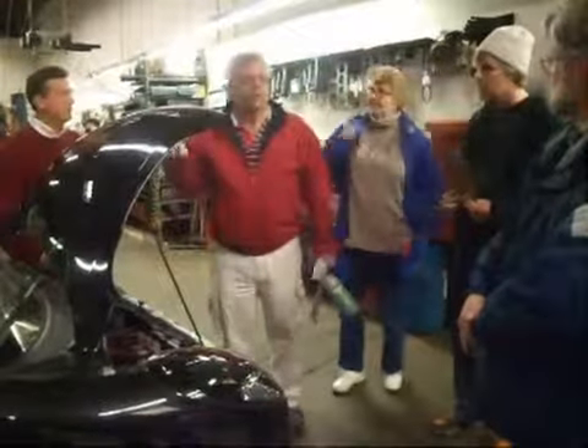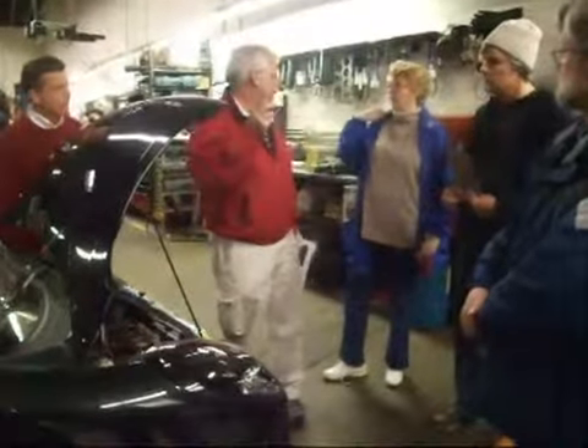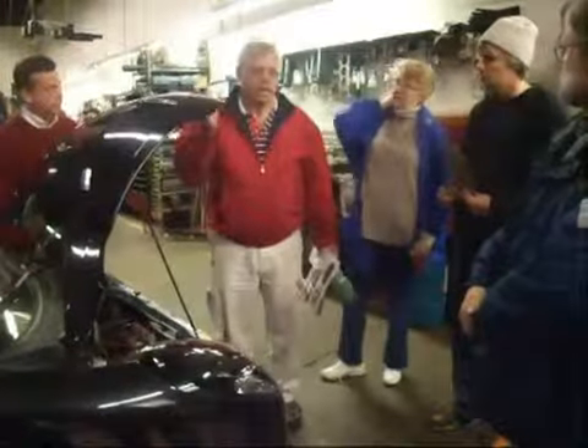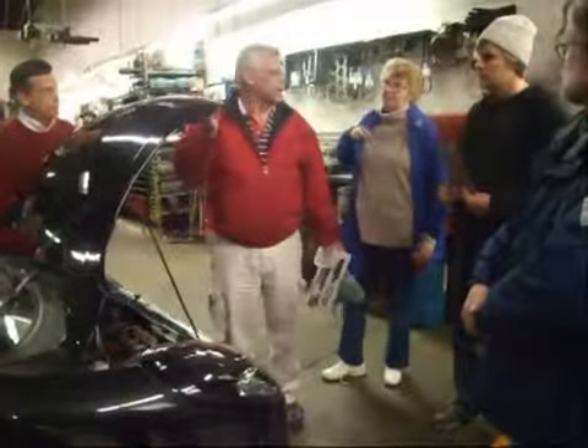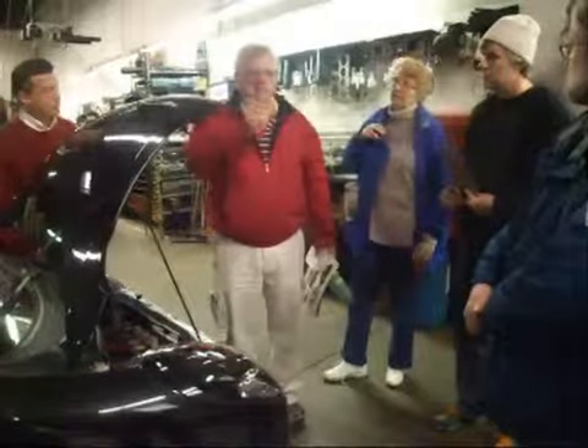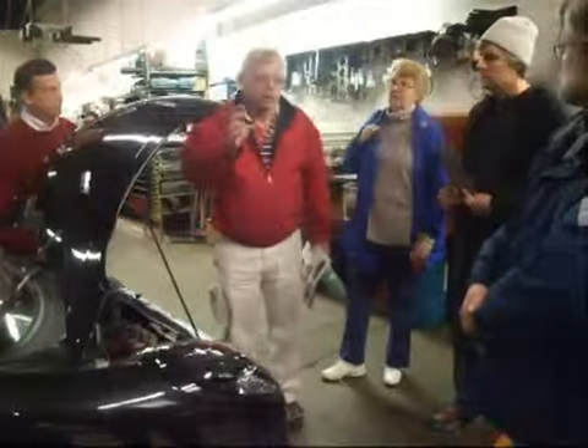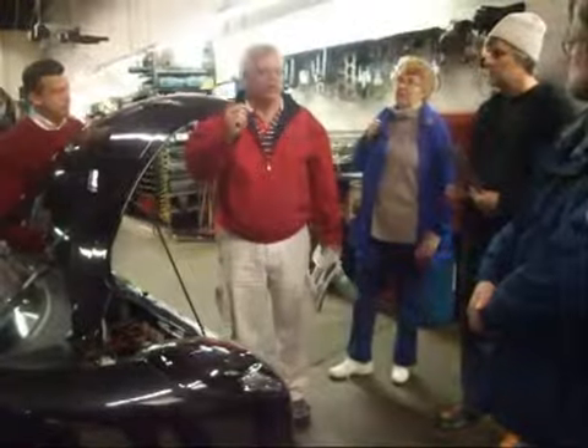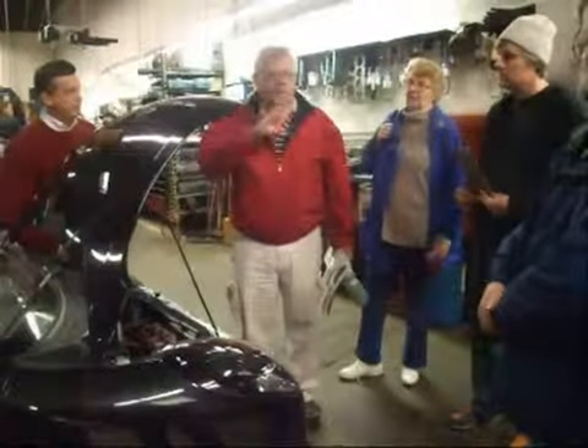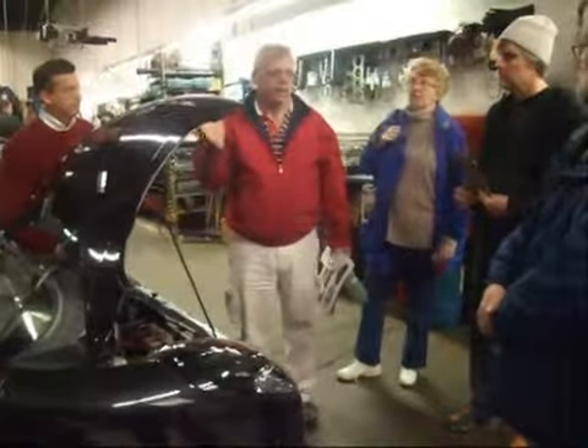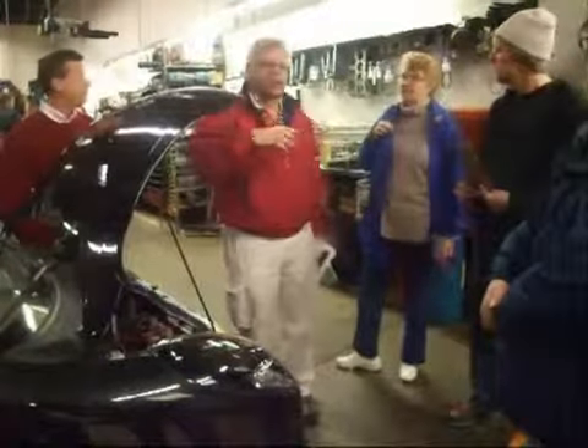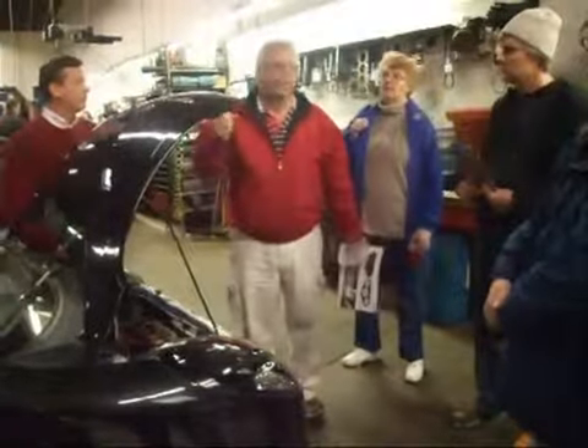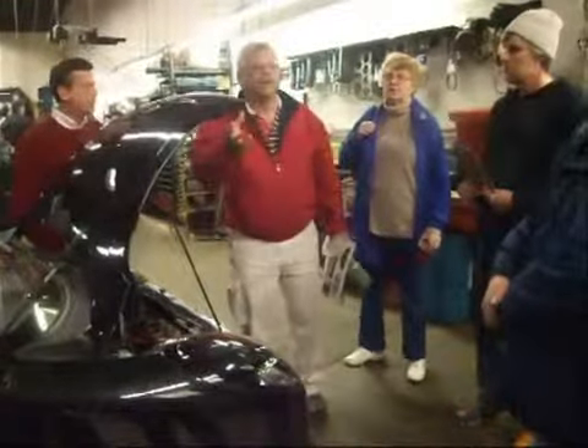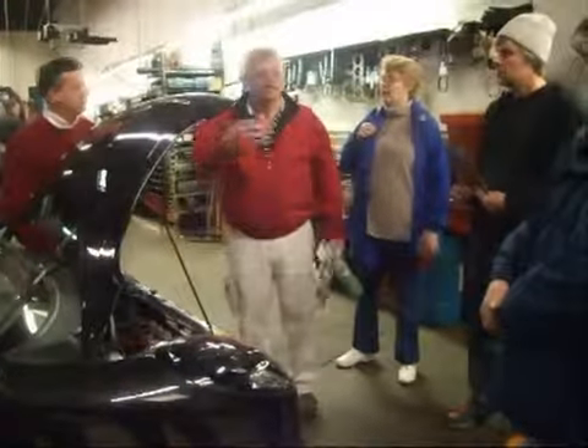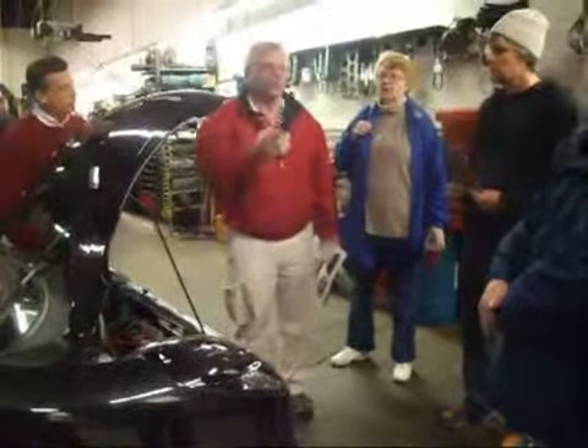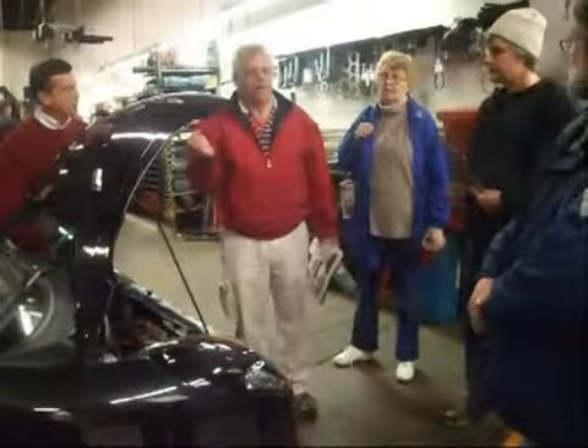This 220 charger runs on 15 amp 220, or 20 amp 220. It's a NEMA R20 or something like that. I hooked one up in my garage, I just bought a few, stuck it in, ran traditional 20 amp cable. It runs on 220, and it's totally up to code. So it's not like a dryer outlet where you need a 40 amp outlet, or an air conditioner one where you need a 50 amp outlet. This is a very small circuit breaker that goes on a standard panel with standard wire.